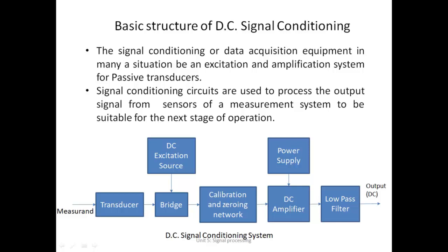And at the output device, it again has to be displayed. Another calibration is to be done in terms of medical units. For example, when you see blood pressure, you don't see it in terms of voltage, you see it in terms of values relevant to blood pressure. All these conversions that are taking place, this is calibration.